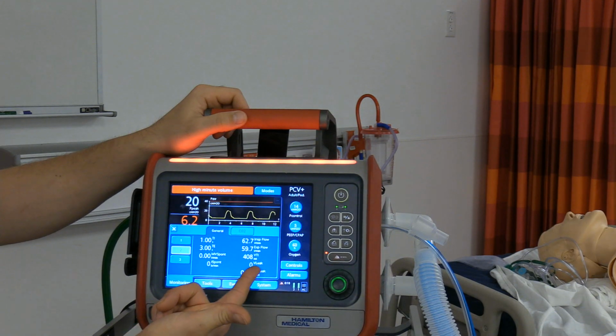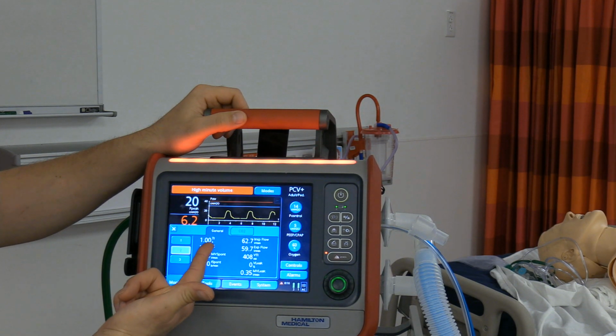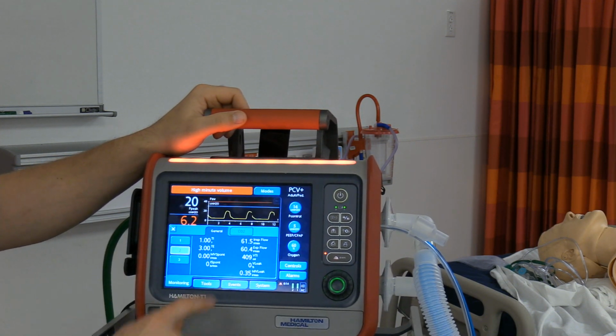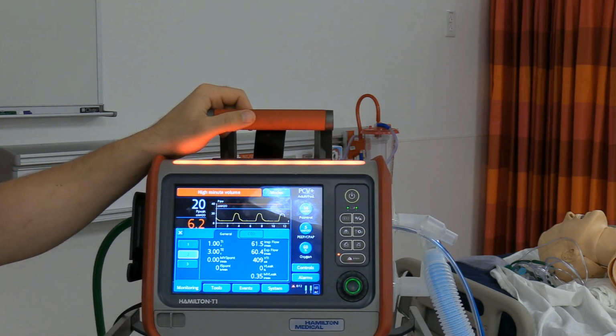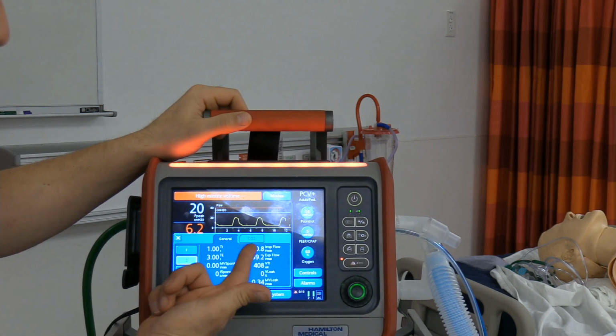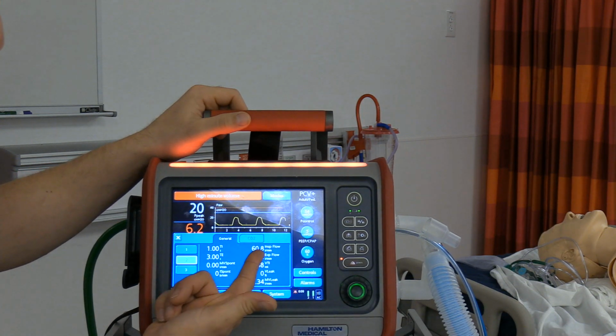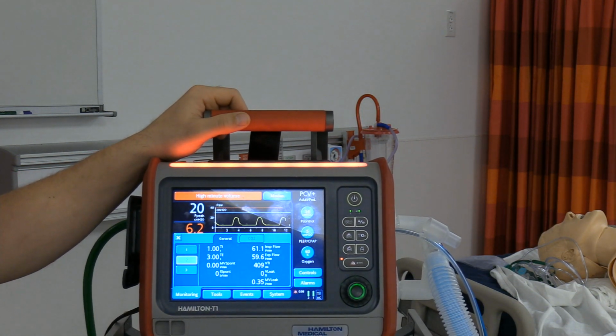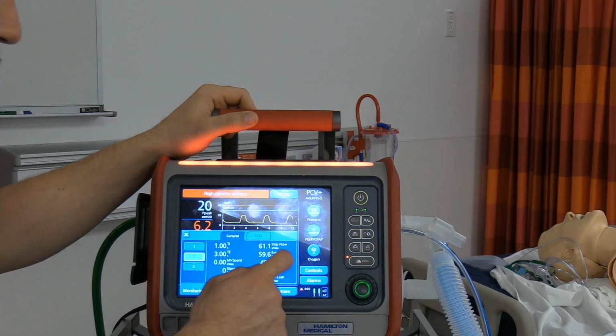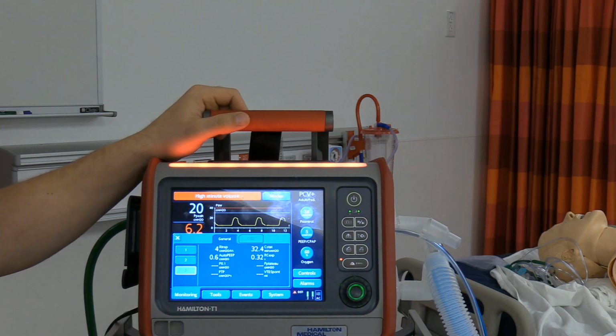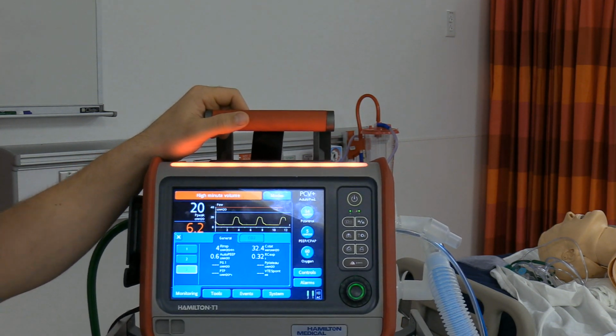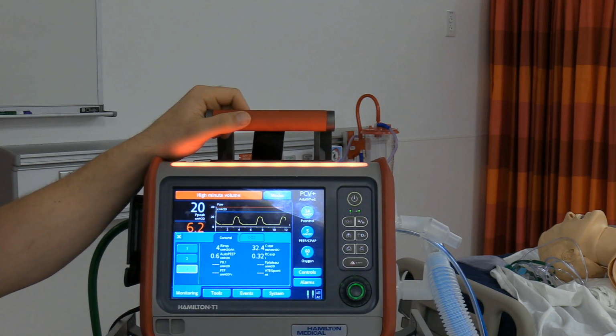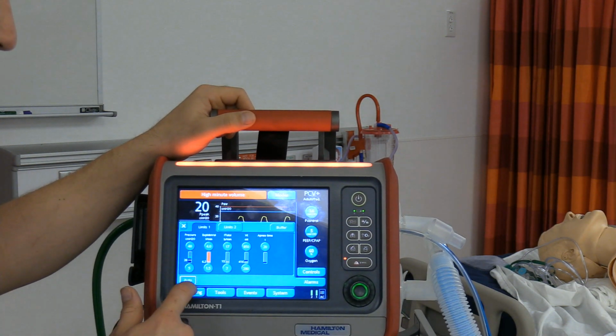Shows me my VTI, shows me if I've got a leak, shows me my I time, E time relations, actual real time. In pressure ventilation, we don't set a flow rate. We're given as much flow as it takes to reach a set pressure, so it does show me what my patient's flow is. All right, hit number 3 here. It tries to do micro pauses and calculate static compliance, time constants, and things we'll get into. I'm going to hit alarms again to hit auto.